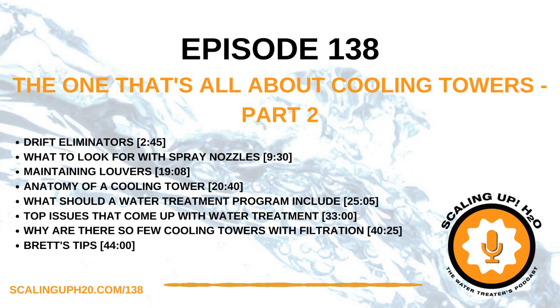That's a huge point to make sure you're getting enough flow rate through the nozzles to give enough coverage, but also that those nozzles aren't clogged up so you're not having a certain area in the fill that's not seeing water, or seeing it sometimes and then not. You're getting the wet-dry effect, which leaves behind scale and deposits.